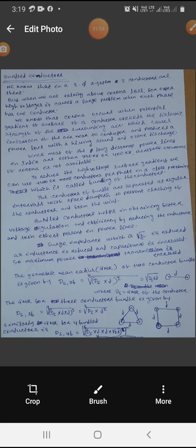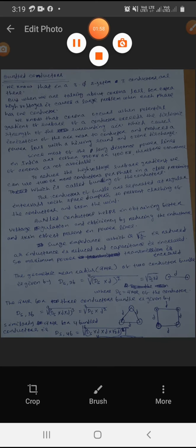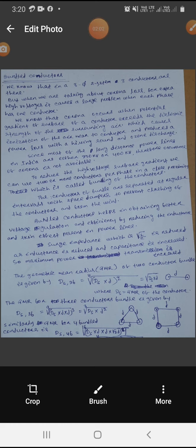In India, as most of the long transmission lines are either up to 220 kV or 400 kV, therefore we can't neglect the corona loss. So we have to think about this when we are making a high voltage line with each phase having one conductor. To reduce the surface gradient at high voltage, we can use two or more conductors per phase in close proximity, and this is called bundling of the conductor. The bundled conductors should be separated at regular intervals with spacers, which prevent clashing of the conductors and also protect them from wind flow.